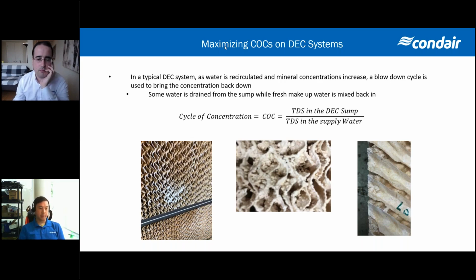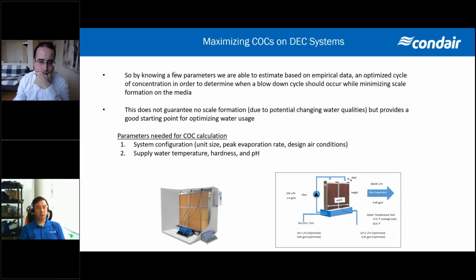Just to give you an idea of some of the scale buildup that we would typically see on the media, if we're running on potable water, it can be as minimal as light sodium buildup if we're running on soft water. In some areas that can be lightly brushed off. But if we're looking at a harder water, potentially with more calcium, we'll see that as a harder scale that can actually block up some of these flutes. And as I'd mentioned, that would increase pressure drop and decrease efficiency on the system as well. So again, it's really just maximizing the water usage versus media life or scaling up on that media.